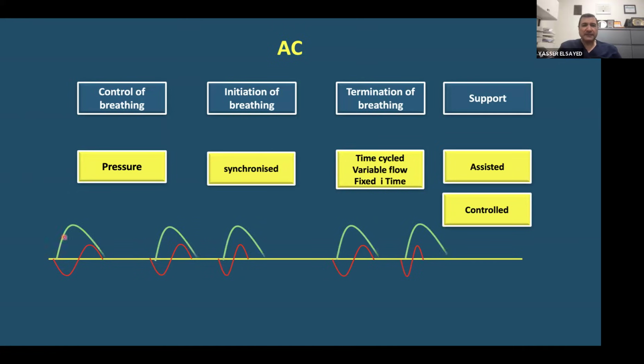So the infant starts to breathe, and the machine gives the breath with the predetermined pressure and I time. And again, the termination is by the machine. So the termination is not synchronized because the I time is fixed. And the expiration, in this case, is passive. So the infant exhales after the preset I time. But again, the expiratory time is controlled by the rate and the I time. So if you give insufficient time for expiration, the infant will be at risk of air trapping. So you have to be sure that the I time and the rate you apply still leave enough expiratory time to exhale all of the air out without air trapping. And I will show you how to detect that on the flow graph.